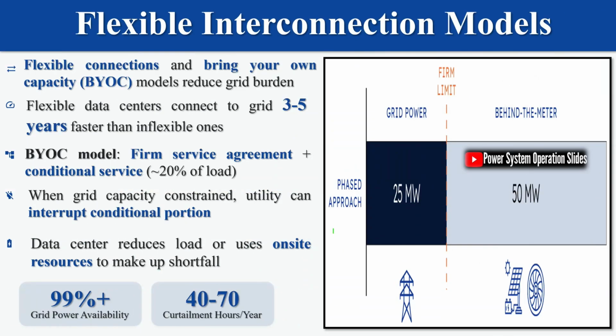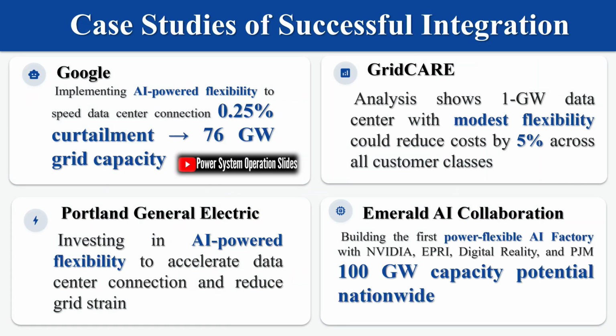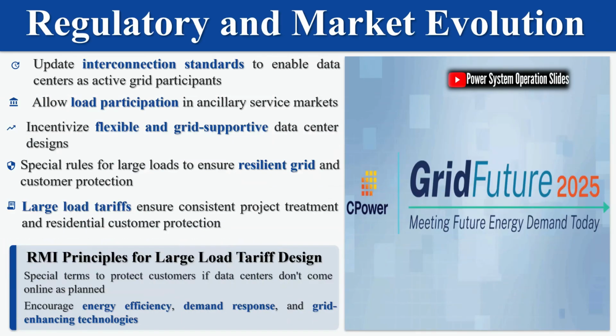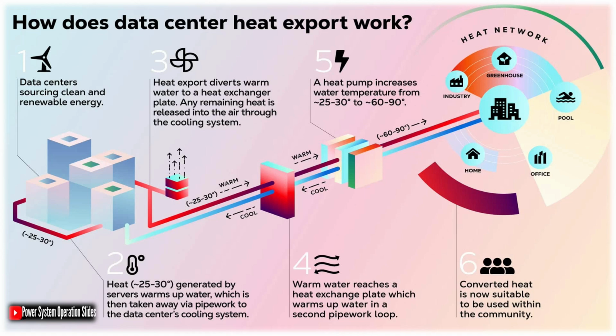These models, often referred to as Bring Your Own Capacity, BYOC, can reduce data center burden on the grid while accelerating deployment. In a BYOC model, part of the load is supported by a firm service agreement and the remainder, about 20%, with conditional or interruptible service. When grid capacity is constrained, the utility can interrupt service on the conditional portion, requiring the data center to reduce its load or use on-site resources to make up the shortfall. Despite these flexibility requirements, data centers would still be able to use grid power more than 99% of the time, with curtailments needed only 40 to 70 hours per year.